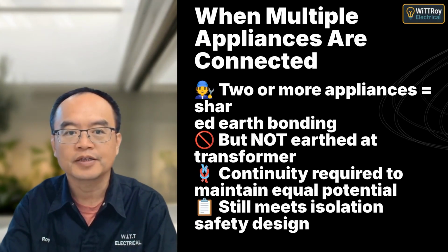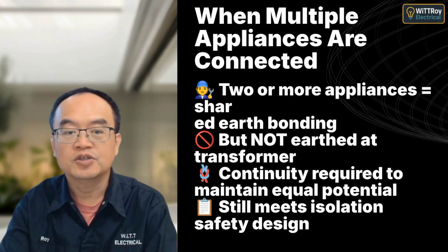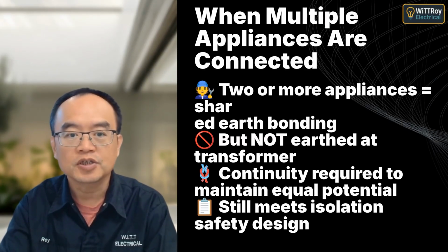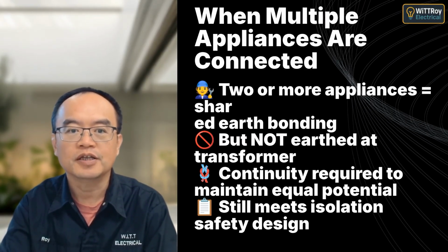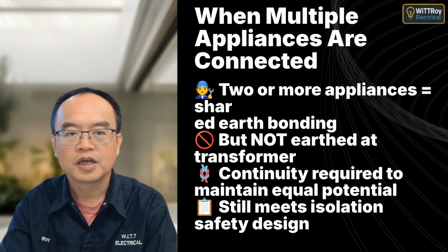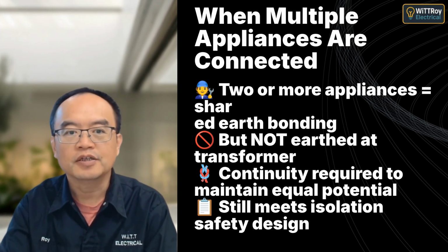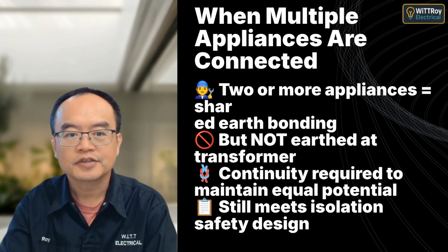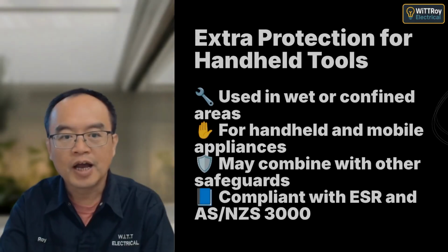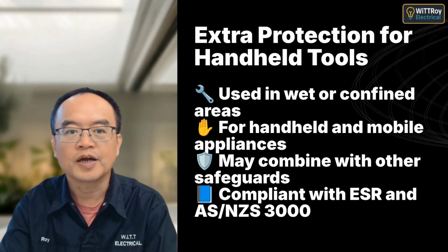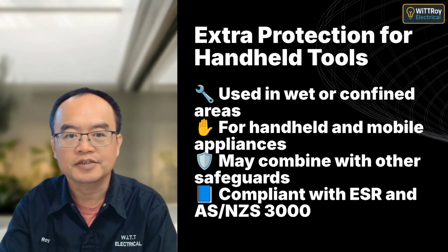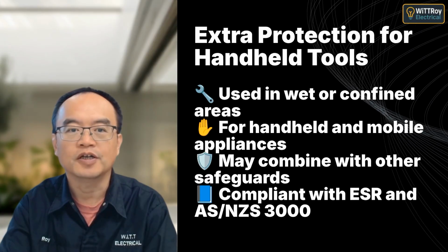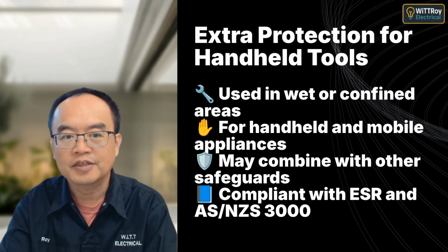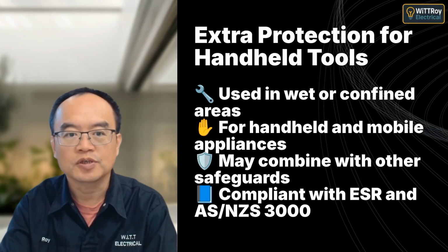If multiple appliances are connected to one isolating transformer, their earth continuity conductors must be bonded together, but must not be earthed. This keeps all exposed conductive parts at the same potential while maintaining isolation. Isolating transformers are often used with handheld tools or appliances in hazardous conditions. They're not always enough on their own, but combined with other protections, they significantly reduce the risk of electric shock.